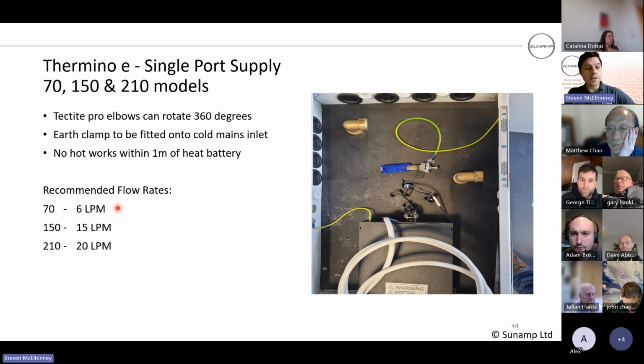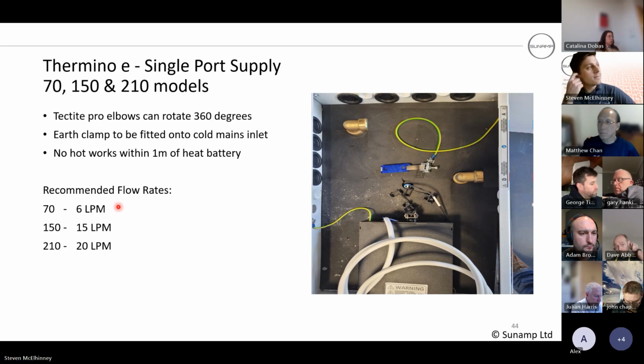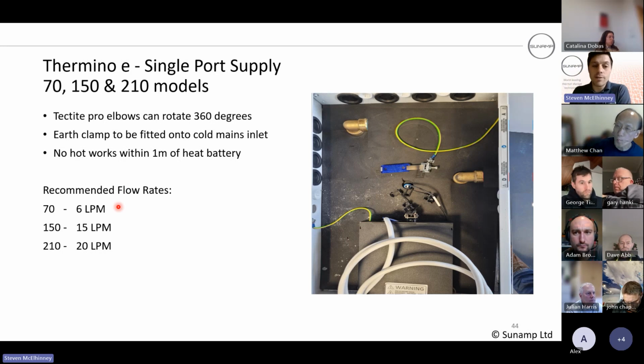So you've got your flow rates here for each of these units. For a Thermino 70, we recommend a maximum flow rate of 6 litres per minute, 150, 15, a 210 up to 20. The 70, for me, 6 litres per minute is not usable for having a shower. That's more for your static caravan type thing. You can push it up a little bit to maybe 8, possibly 10. You just have to be aware, the faster that water's running through the heat exchanger, the less chance it has of catching the heat. So you could be introducing capacity issues for the customer, especially in the winter time, when that cold mains is colder coming into the property. Okay.